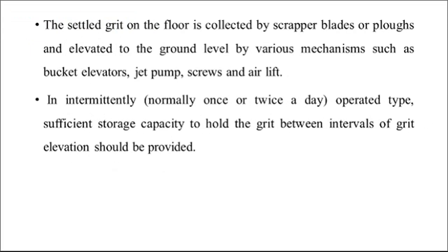The settled grit on the floor of the grit chamber is collected by scraper blades or plows and elevated to ground level by various mechanisms such as bucket elevator, jet pump, screws and airlifts. In intermittently operated types of grit chamber, sufficient storage capacity should be provided to hold the grit between the intervals of grit elevation.